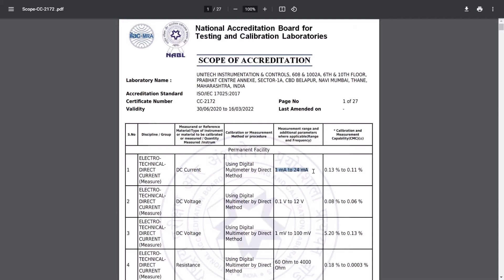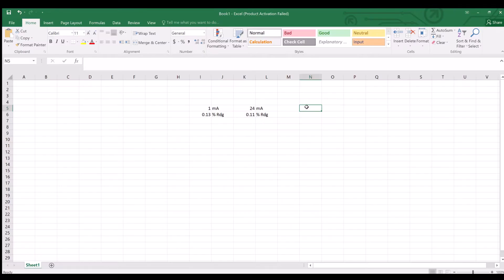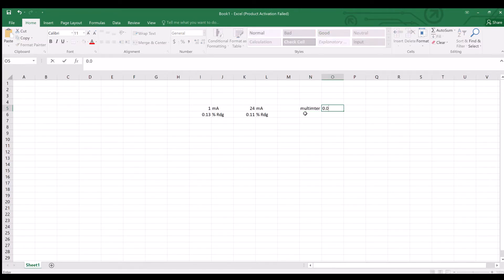This is my CMC: 0.13% to 0.11% using a digital multimeter by direct method. Now this multimeter has some resolution. For example, this multimeter has a resolution of 0.0001 milliampere for this range, so the range is given as 1 milliampere to 24 milliampere.